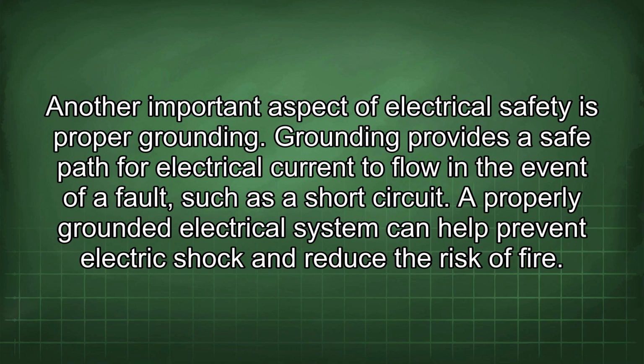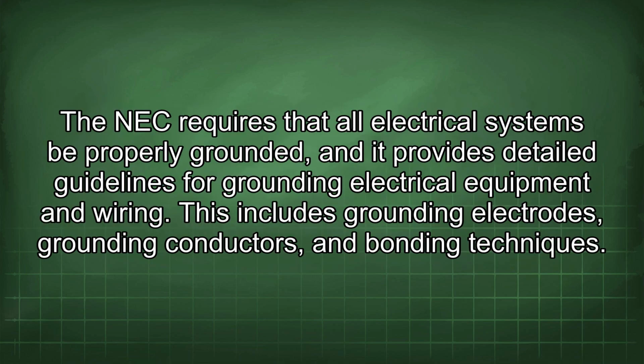Another important aspect of electrical safety is proper grounding. Grounding provides a safe path for electrical current to flow in the event of a fault, such as a short circuit. A properly grounded electrical system can help prevent electric shock and reduce the risk of fire. The NEC requires that all electrical systems be properly grounded, and it provides detailed guidelines for grounding electrical equipment and wiring. This includes grounding electrodes, grounding conductors, and bonding techniques.